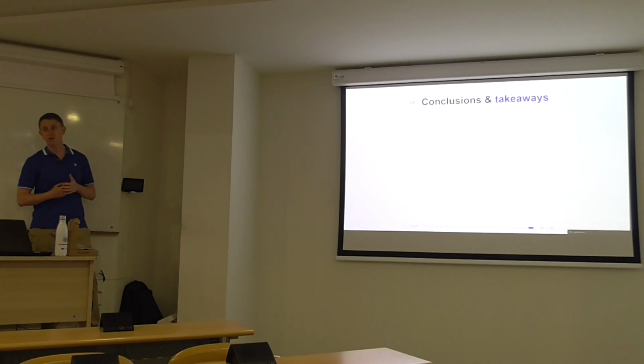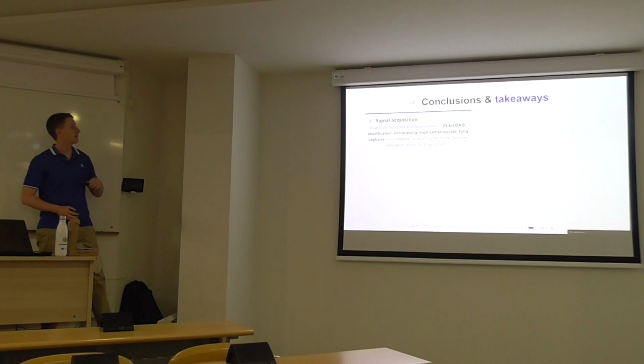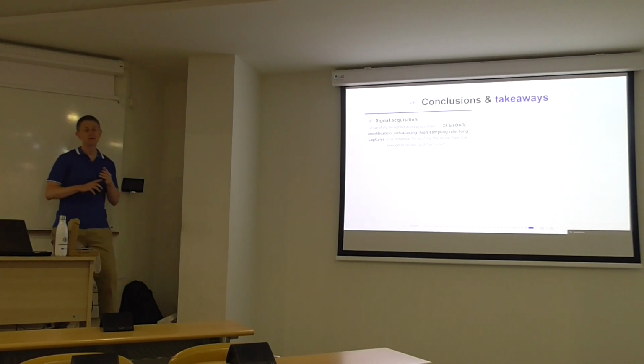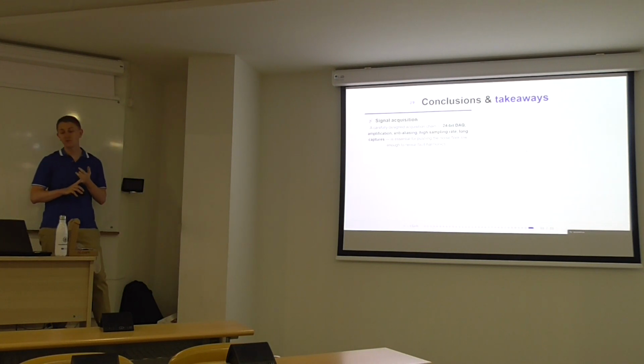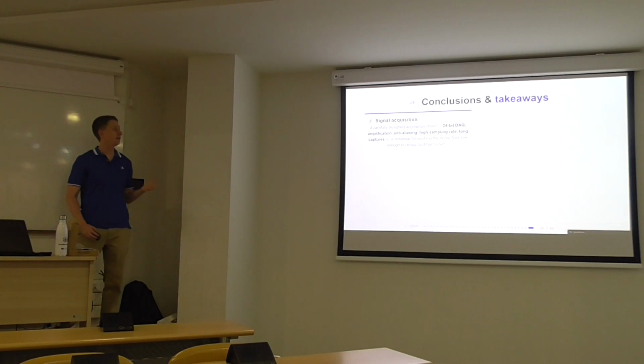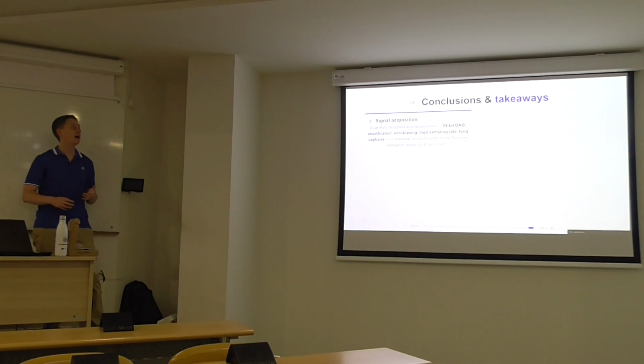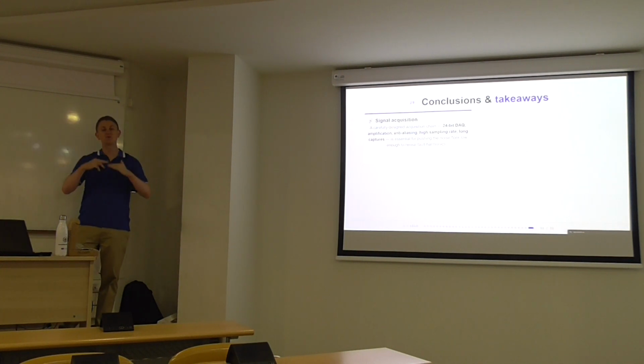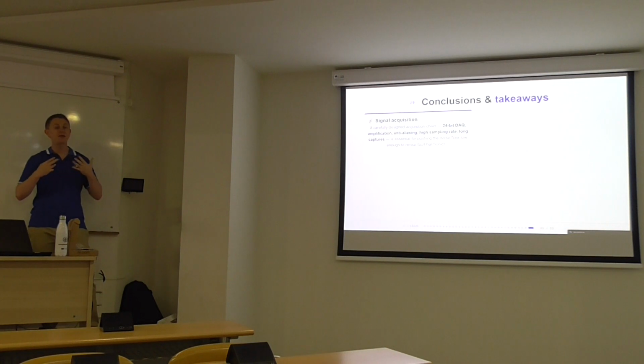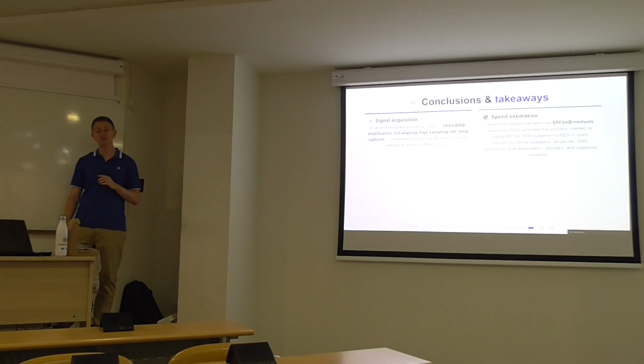So, conclusions and takeaways. Regarding signal acquisition, remember, you need a carefully designed acquisition chain: a 24-bit data acquisition system, an amplifier, an anti-aliasing filter, a high sampling rate, and a long acquisition time. All that is essential to keep the noise as low as possible and make the harmonics visible in the spectrum.